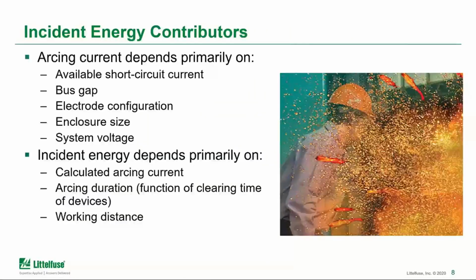So it's important to look at what are the points that contribute to the severity of an arc flash or the incident energy itself. So this is just a brief overview, not really intending to get scientific. There's a lot of great papers out there. So if there's questions on that, I can certainly help point to some that I've read. But generally, when we're talking about the thermal energy, we talk about I squared T, something like a thermal capacity of a motor. But for incident energy, we need to review some of the other factors. And here it's shown as two bullets. First, looking at the arcing current, and then looking at the resulting incident energy.